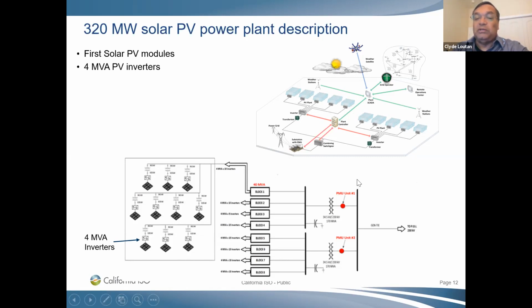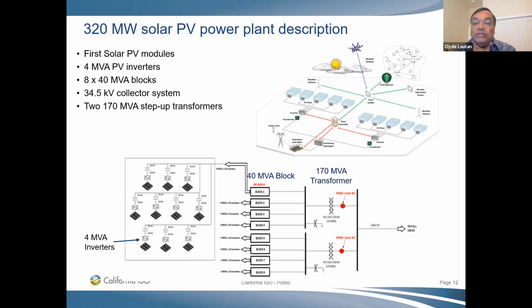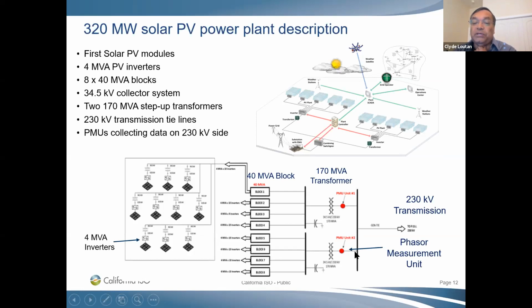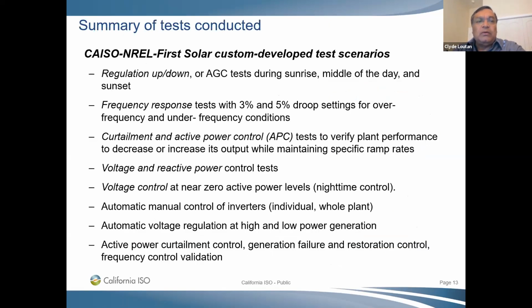The plant controller would precisely control the movement of that plant. Now, before we did the test, right here, these 2 red dots, we installed some phasor units, and that was really to measure the response from the plant to the test signals that we sent. Now, the test that we embarked on was basically regulation up, down, frequency response.